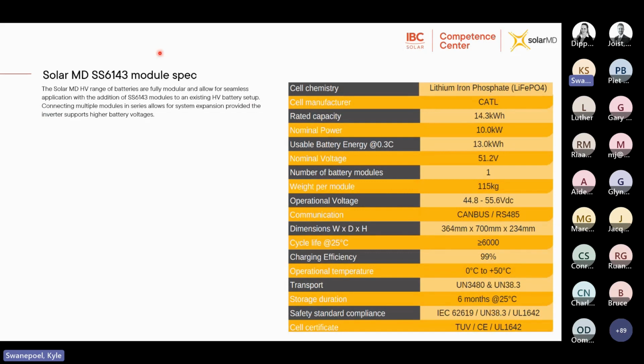Okay, just to quickly run over what I mentioned now, the SS6143 battery module allows for expansion on an existing system. So if you were to start with an SS7011 and wanted to increase the capacity without buying another battery, you can add more modules, but obviously adding more modules will increase the voltage. So again, just check that you're within the voltage range of the inverter. And here are the specifications of that module, which is the same as the SS214. It's 14.3 kilowatt hours, 10 kilowatt rated power, 51.2 volts, and that's it in a nutshell.